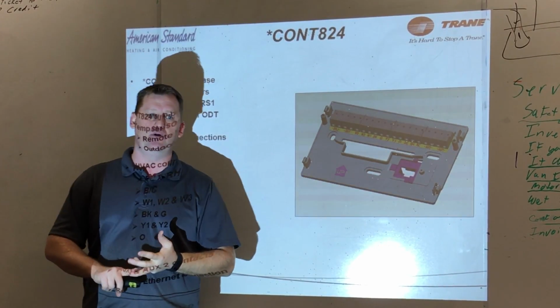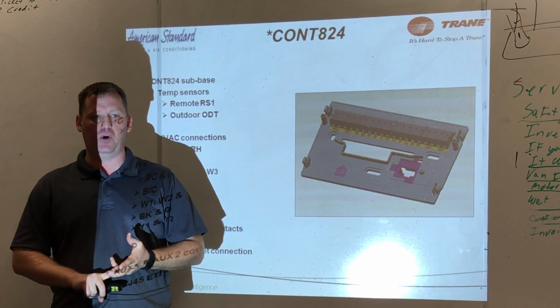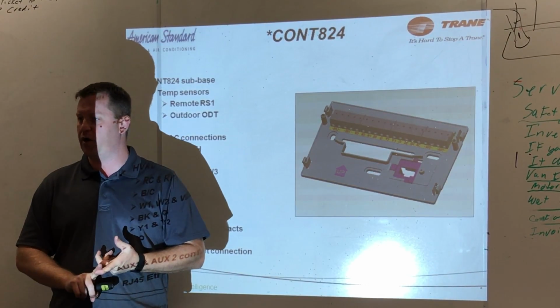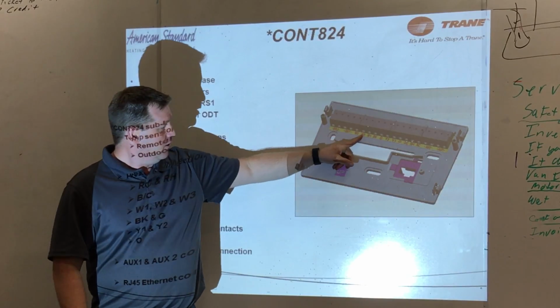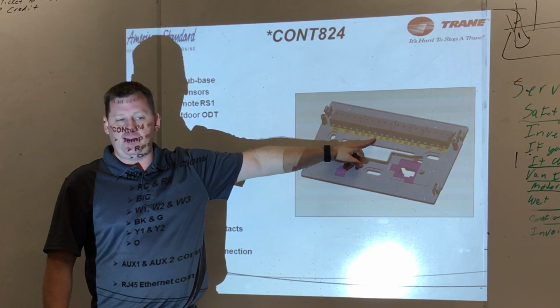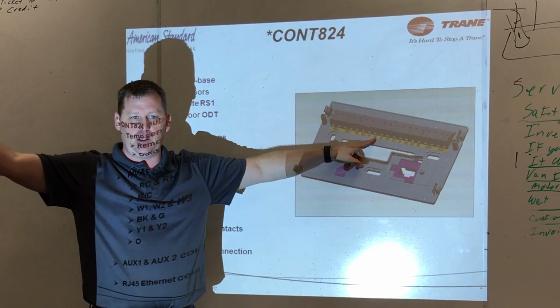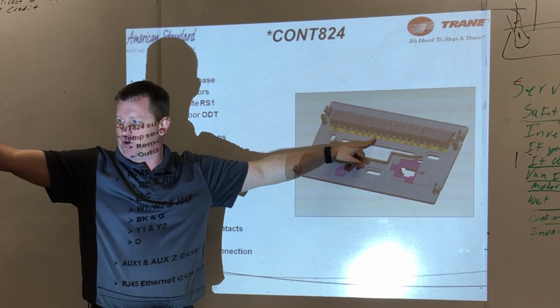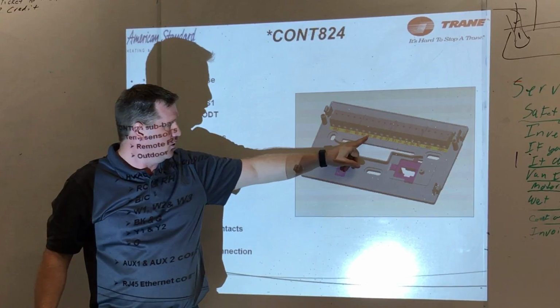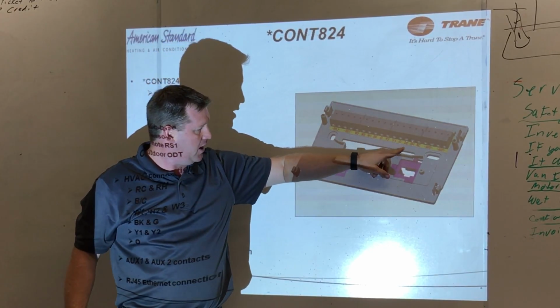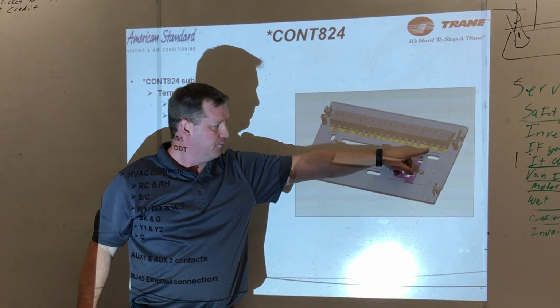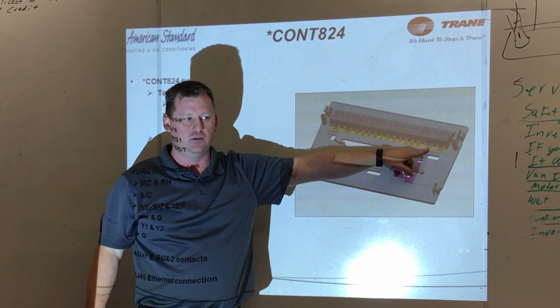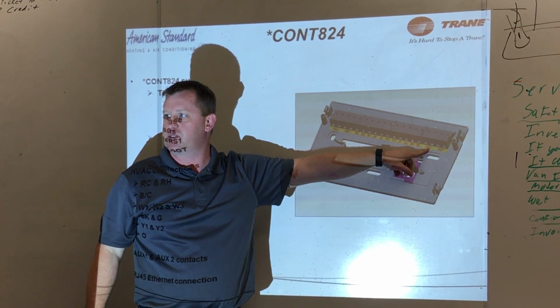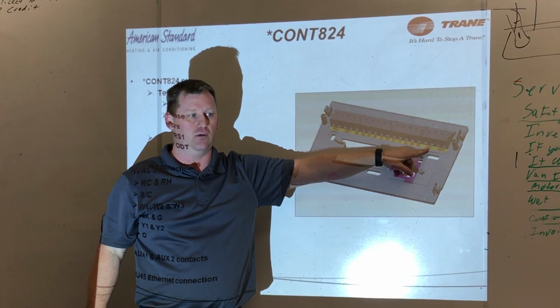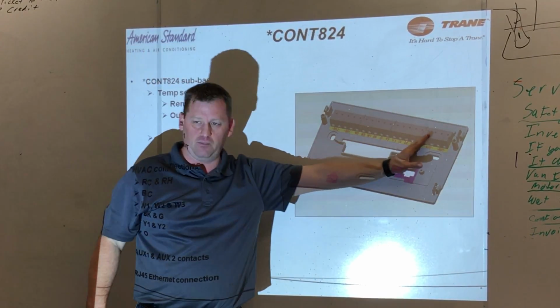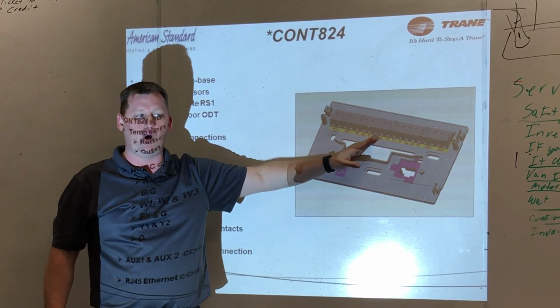If you're on a TAM7 with a 2-stage outdoor heat pump and a humidifier, you'd want to use that BK terminal, wiring BK to BK and cutting the BK jumper so the stat controls the variable speed fan. That's 1 through 10, plus 2 more for the humidifier. How many times do we have 12 wires in a stat? Never, so we may have to pull new wires for this one.